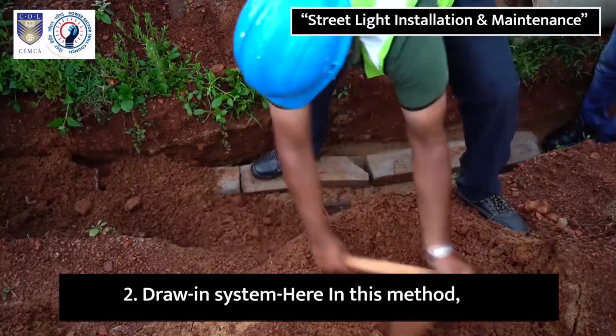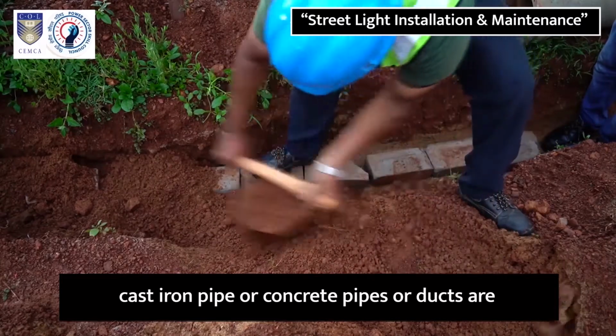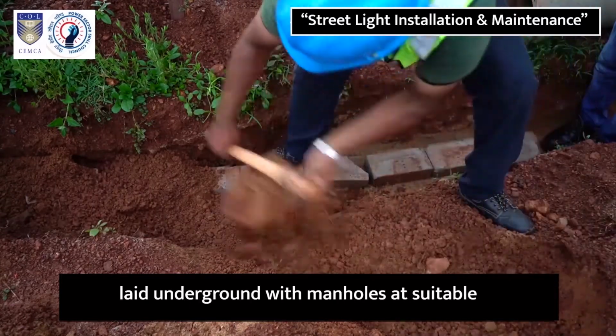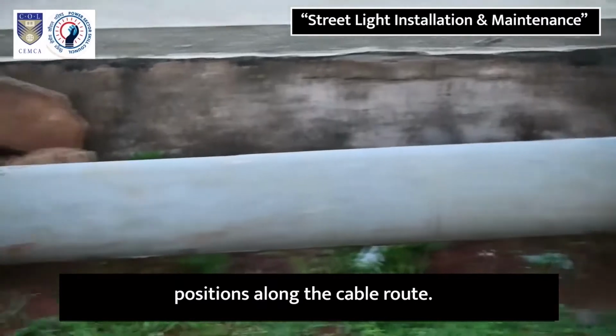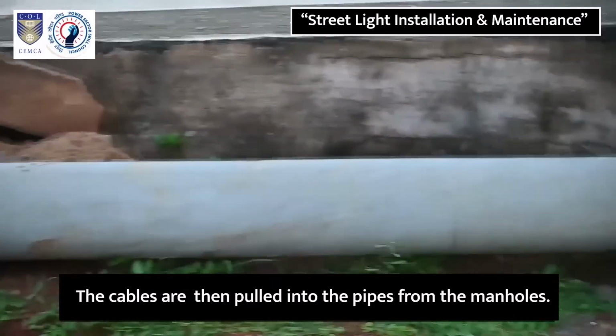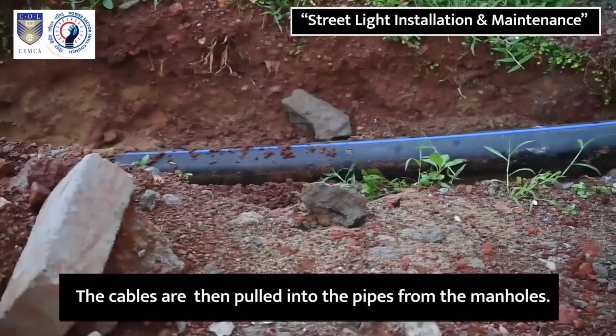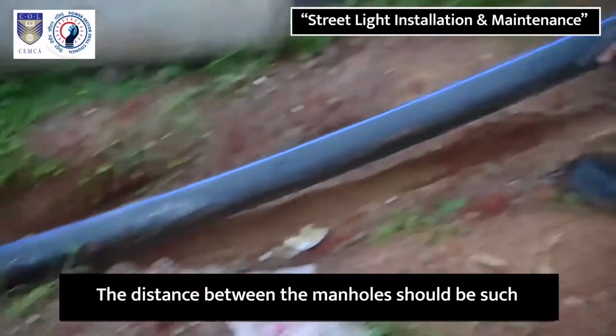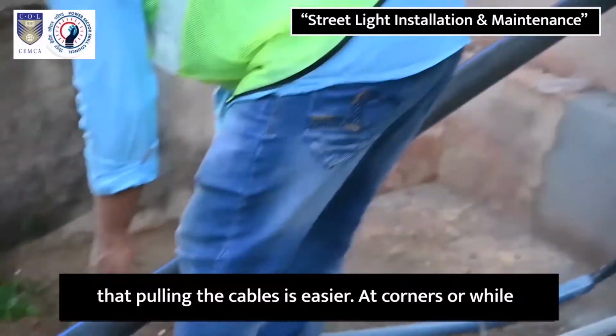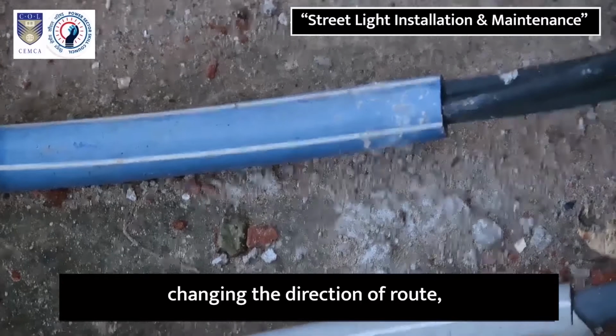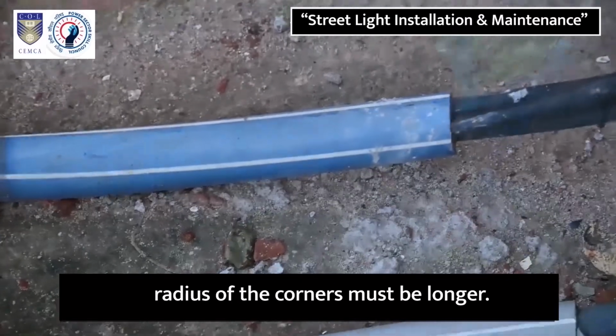2. Draw-in system. Here in this method, cast iron pipes or concrete pipes or ducts are laid underground with manholes at suitable positions along the cable route. The cables are then pulled into the pipes from the manholes. The distance between the manholes should be such that pulling the cables is easier. At corners or while changing the direction of route, radius of the corners must be longer.